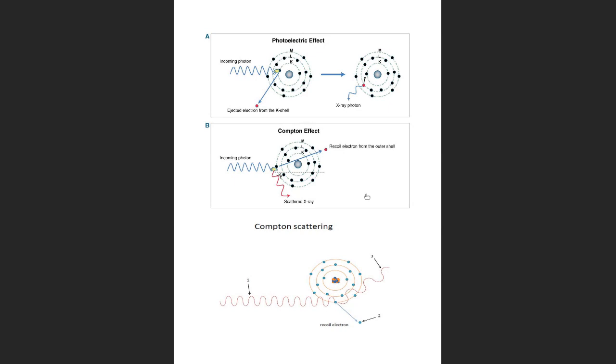So we try to do things like, I don't know, not stay in the room. We need to be far enough from the patient to not be affected by Compton. We want to wear lead to attenuate the Compton scattered photons that could affect us. So there are all these things that we do, our cardinal principles, right? Time: spend as little time in the room as possible. Distance: we want to have at least 6 feet. Standing behind the shield, our barrier, in the control booth, and wearing lead. Those are all things that we do to protect ourselves from Compton, because Comptons are our problem.